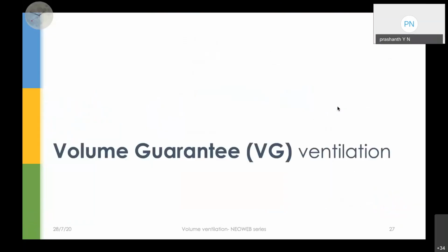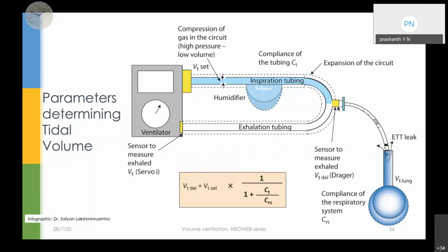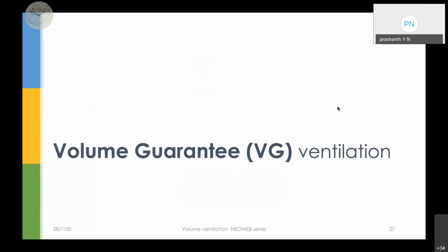To compensate for these fallacies, just mechanically pushing the air into the circuit is not working, we know that. To make it more intelligent, Draeger came up with this modality of ventilation called volume guarantee ventilation. Mind you, volume guarantee is used by Draeger ventilators. Other ventilators use the same principle but different words. For all practical purposes, we'll be using volume guarantee or targeted volume ventilation in this talk.